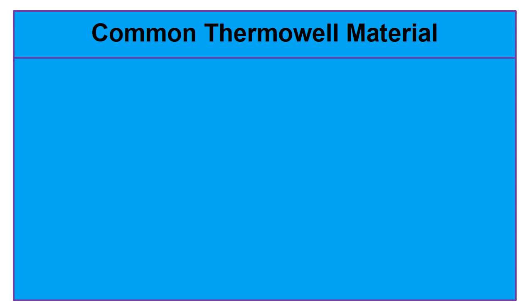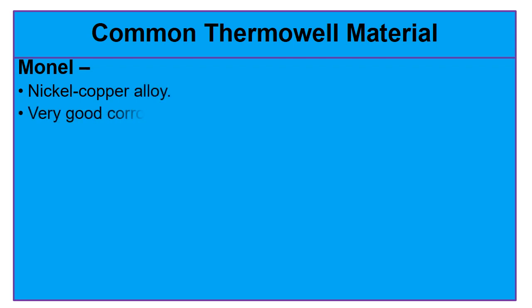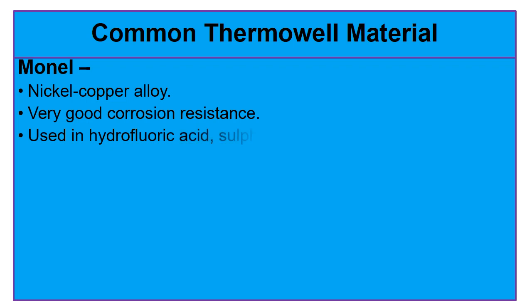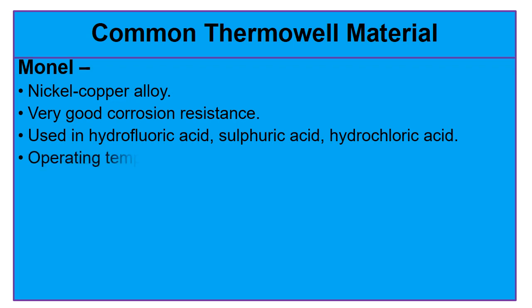The next material is Monel. Monel is a nickel-copper alloy with very good corrosion resistance. It is commonly used to handle seawater, hydrofluoric acid, sulfuric acid, and hydrochloric acid. The maximum operating temperature of Monel is 530 degrees centigrade.